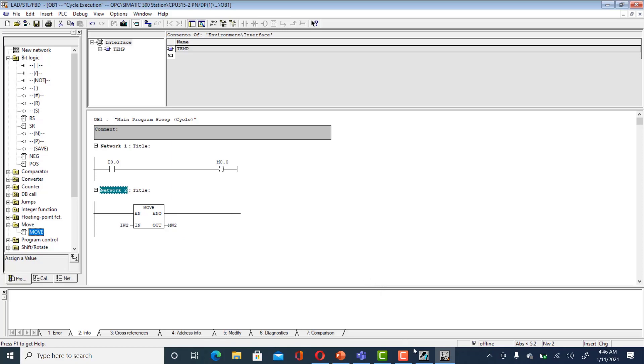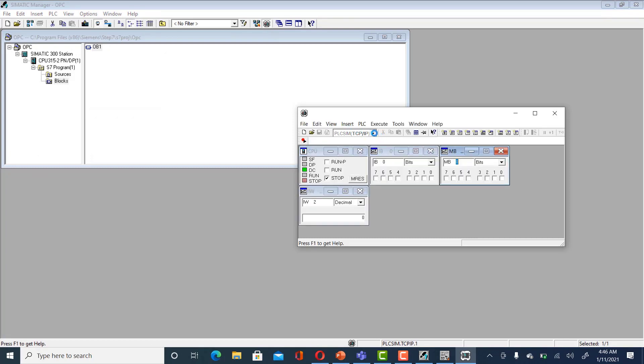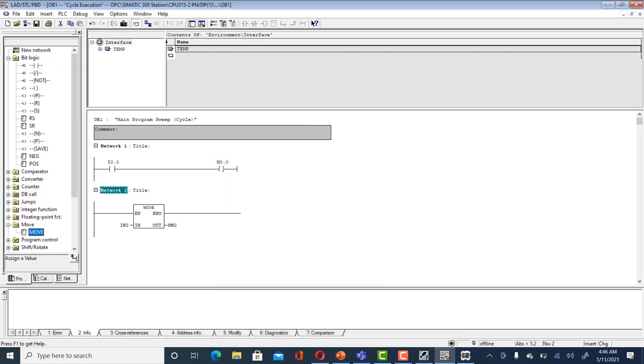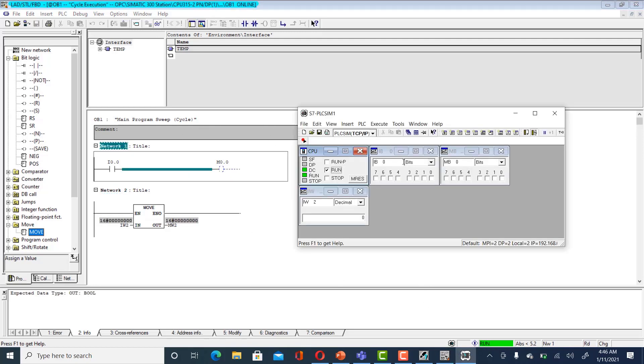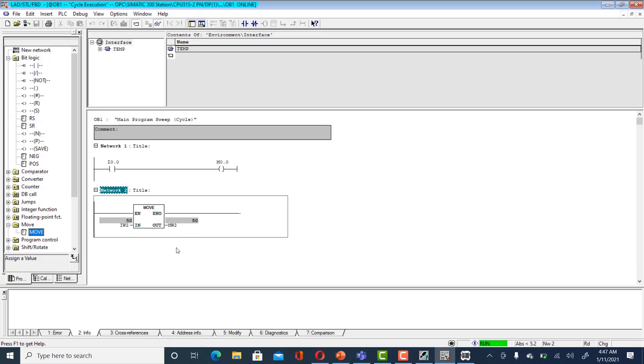Let's simulate quickly using PLC Sim. Download and run the program, turn on the simulation. When you press I0.0 you see M0.0 go high. If you give a value of 50, you should see 50 appear. Change the representation to decimal and you can see IW2 with value 50 is moved to MW2. Now let's get that data onto the OPC server.